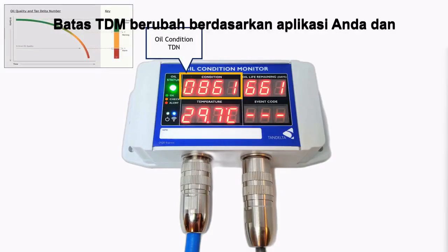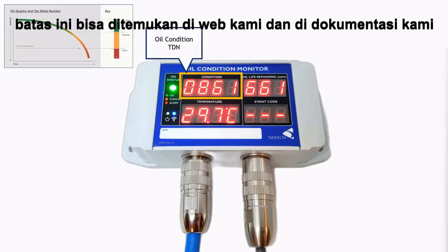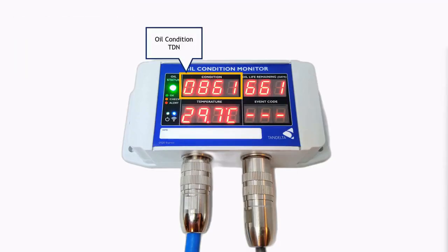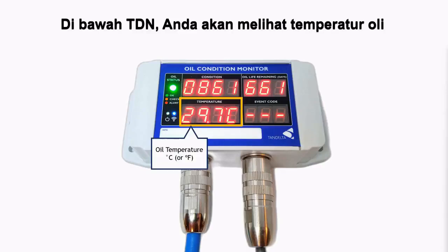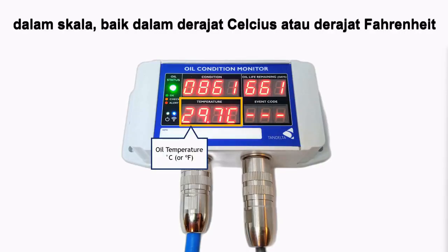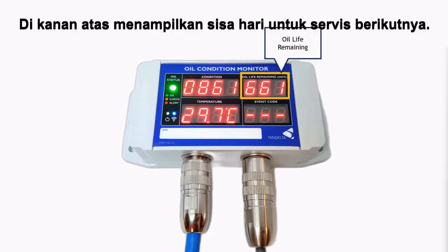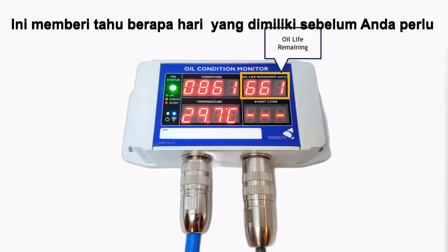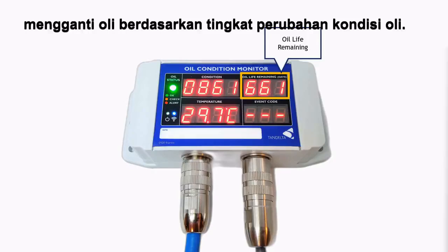The TDN limits change based on your application, and these limits can be found on our website and in our documentation. Below TDN, you have the oil temperature, which is displayed in your preferred scale of either degrees Celsius or degrees Fahrenheit. The top right-hand box displays the days to the next service. This tells you how many days you have before you'll need to change the oil, based on the rate at which the oil condition is changing.